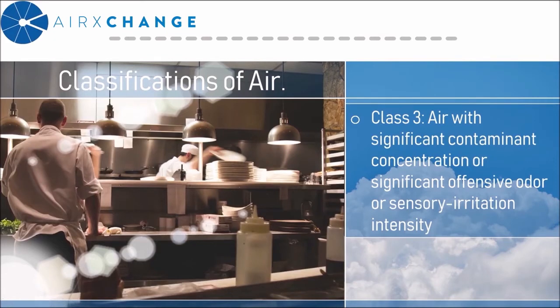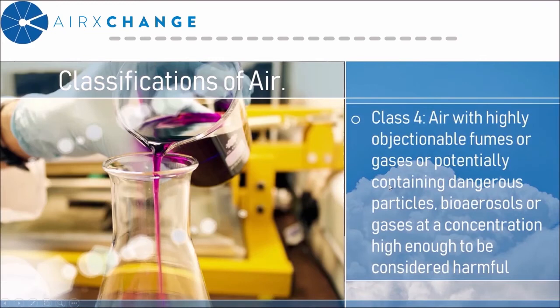Class 3 air is air with significant contaminant concentration or significant offensive odors — examples of this type of space include kitchens, dry cleaners, beauty salons, and pet shops. Class 4 air is air with highly objectionable fumes or gases, or potentially containing dangerous particles. This would be your lab and process exhaust — examples include paint spray booths, laboratory fume exhaust, and kitchen grease exhaust.